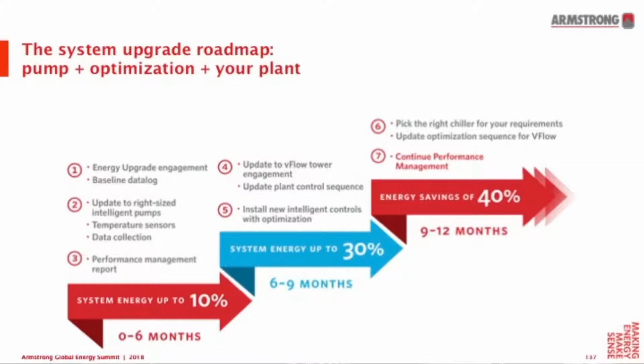In summary, as I shared earlier, you start with the pump and save 10%, learning from the flow and all the intelligent analytics the pump generates. Then take the next step, which from our experience is primarily around upgrading the towers or converting them to variable flow, for 30% of energy. Then you go to chiller optimization or chiller resizing, which gives you another 40% of energy.